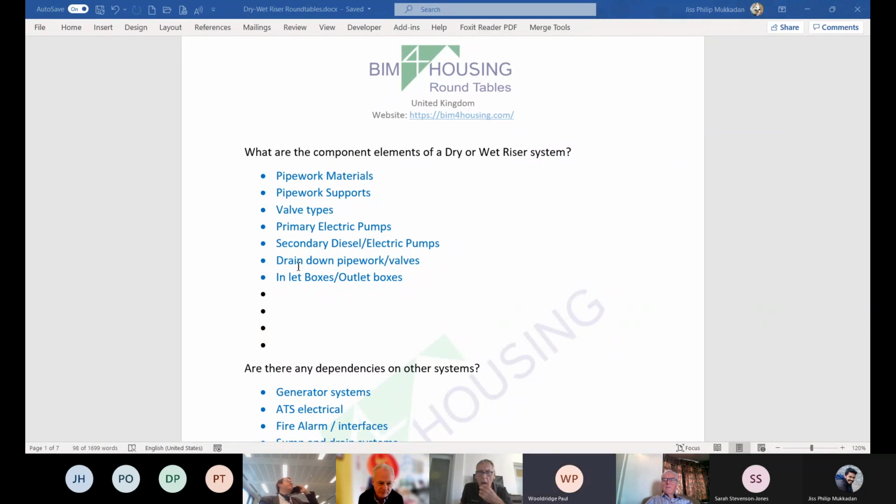Paul. Yeah, I just agree with those comments very strongly. We've been approached by a lot of contractors that are promoting these systems. My concern is a lot of them that we've seen the approaches from have closed protocol systems, and the maintenance is cost prohibitive, shall we say. And there's no justification for putting them in. I've seen a lot of project managers on the development side come to me and say, look, I'm being pushed for this as an alternative to a sprinkler.